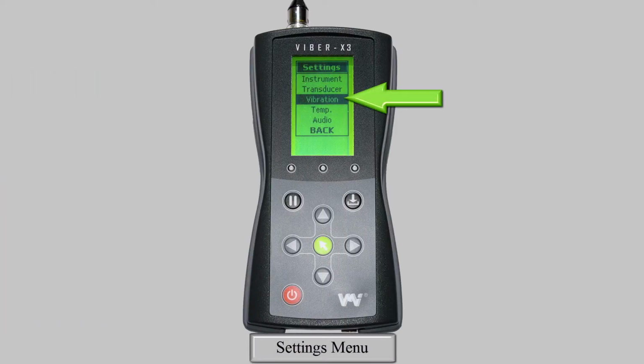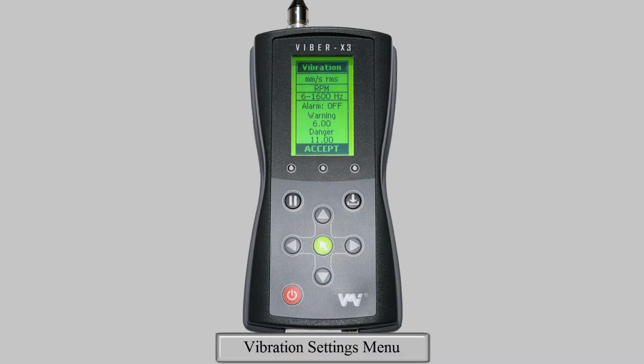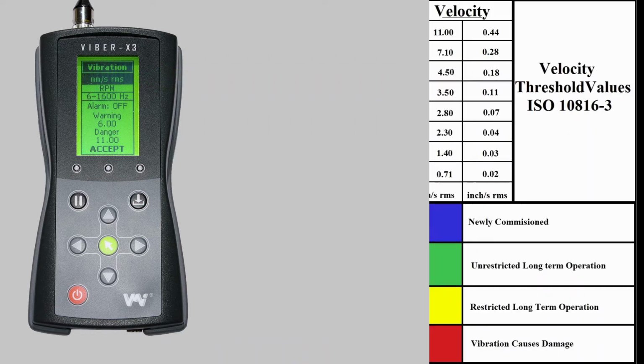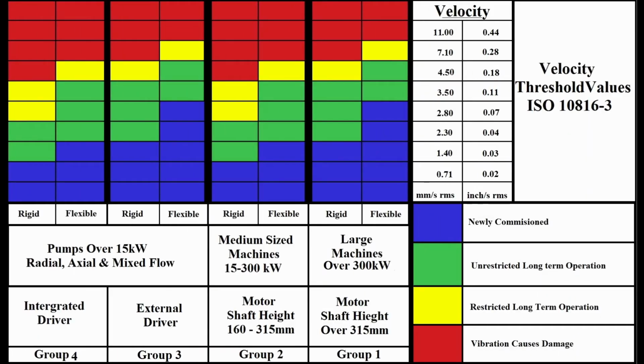The next submenu is for the vibration measurement settings. Here you can select the units you wish to measure in, change your frequency range, and set your alarm levels. After selecting this submenu, use the up and down arrows to highlight the option you wish to change, and then use the left and right arrows to move through to the required setting. The top setting is for the units of your vibration measurement. VMI recommends using millimeters per second RMS, as this is the unit used in ISO 10816-3. Use this standard to assess your readings and determine whether further investigation or corrective maintenance is required.